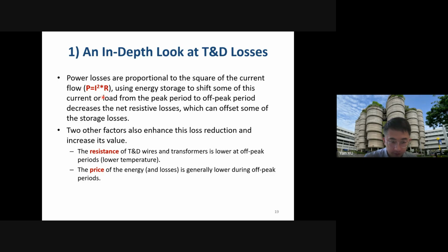Later I will introduce this, but first we need to understand that in addition to the current, the resistance of the transmission and distribution wires and transformers is also variable. It depends on the external ambient temperature, so this resistance is lower at off-peak period and relatively higher at peak period, because the temperature is high.